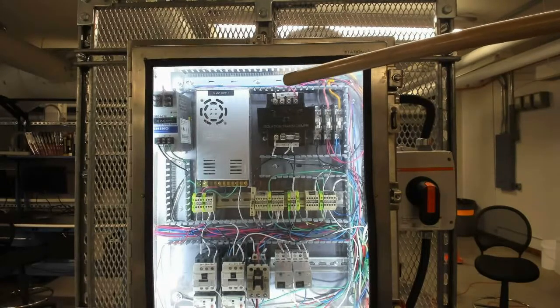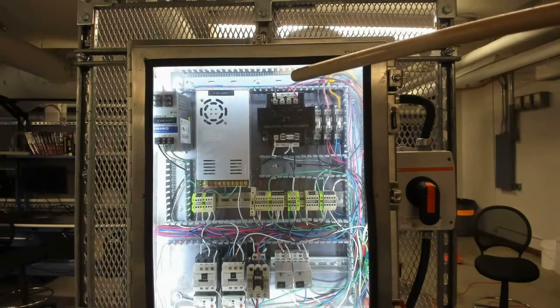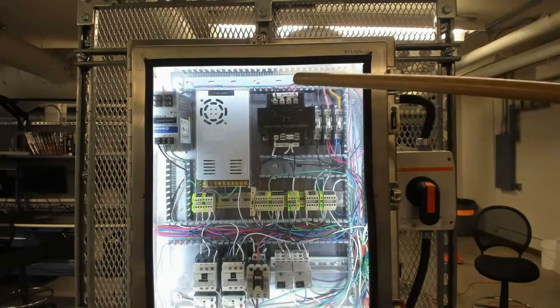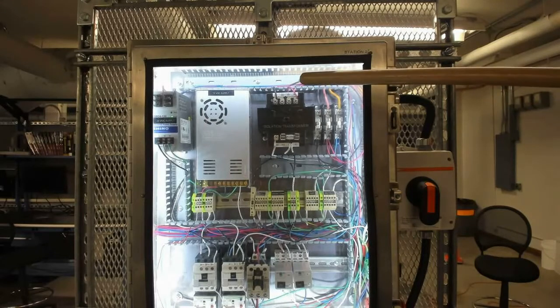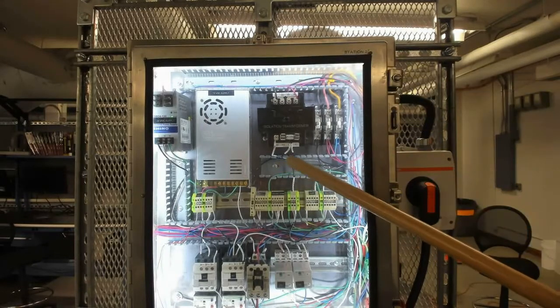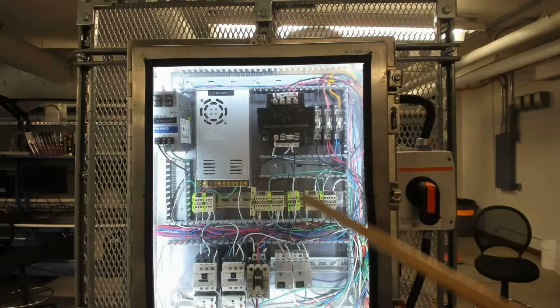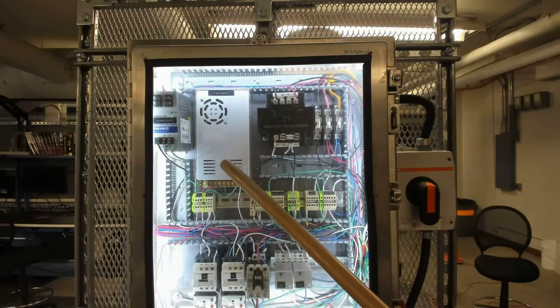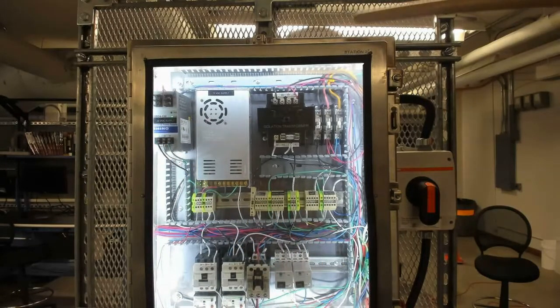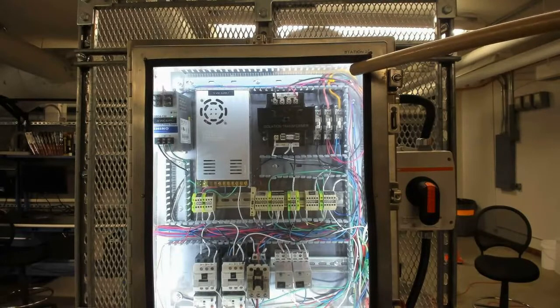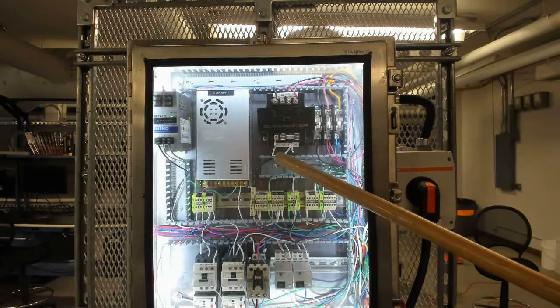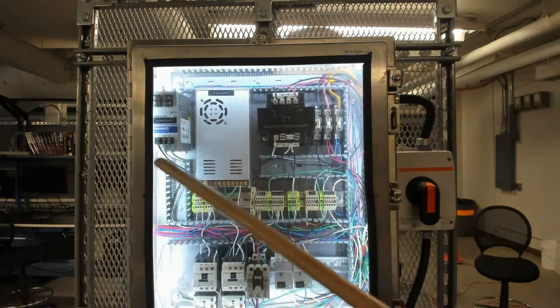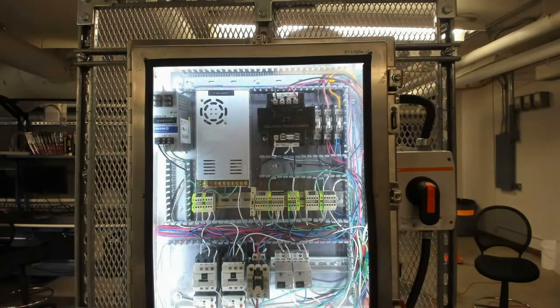And then in this system we have an isolation transformer, so we can isolate. We have 208 3-phase on this side. We bring up 2 of the phases, and then down here we bring out 110 volt single phase AC. Then we have a 12 volt power supply and a 24 volt power supply. So inside this enclosure there's 208 3-phase, 110 volt single phase, 12 volts DC, 24 volts DC. All those different voltages are required to run the different pieces of equipment on the training skid.